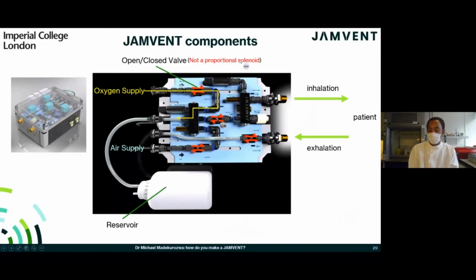Note that these valves are not proportional solenoids. Typically in high-end systems that perform similar to the JAMVENT system, proportional solenoids are used. But the problem with proportional solenoids is they are specialist components, which makes them difficult to source. So we went with on-off valves instead, and these on-off valves are much, much easier to procure.